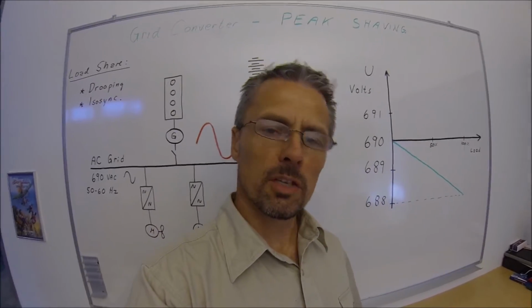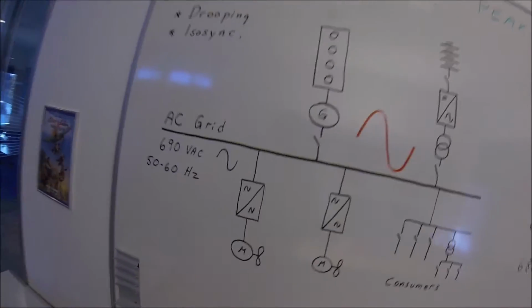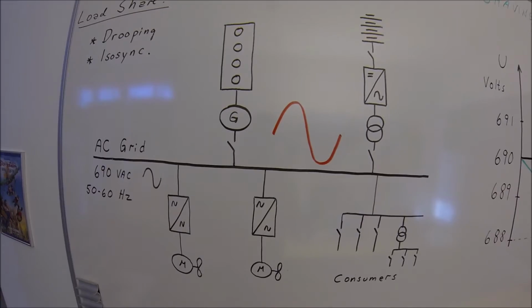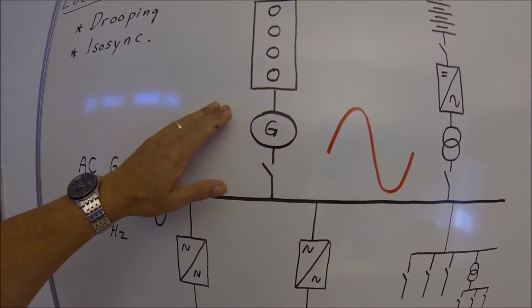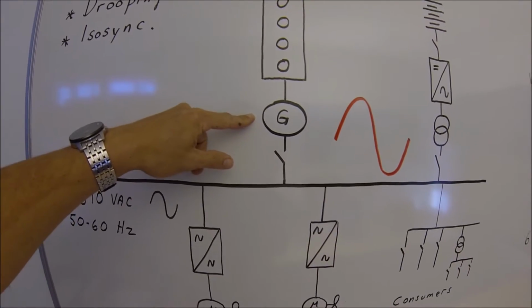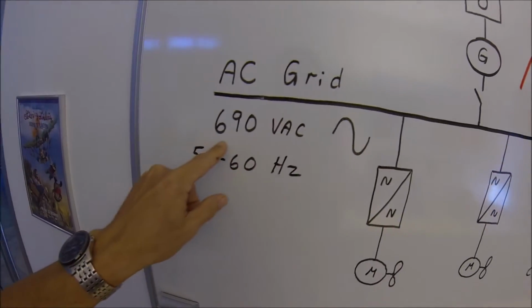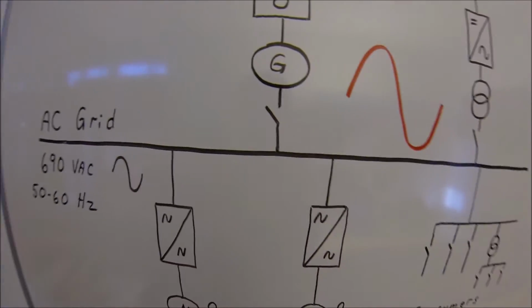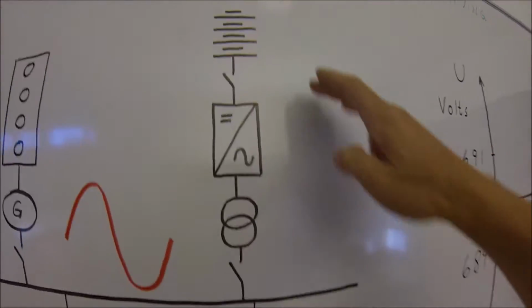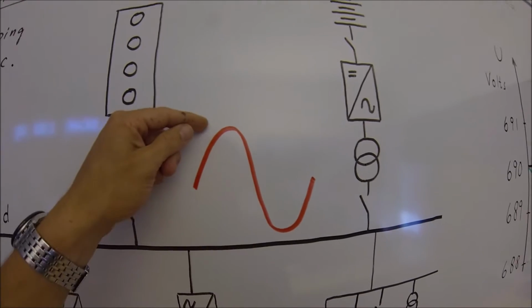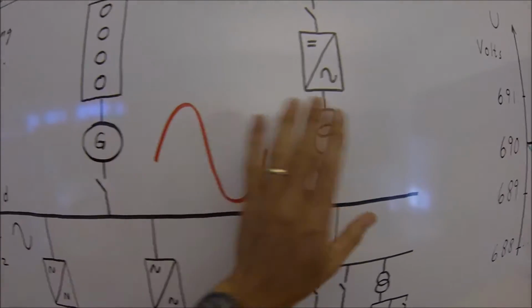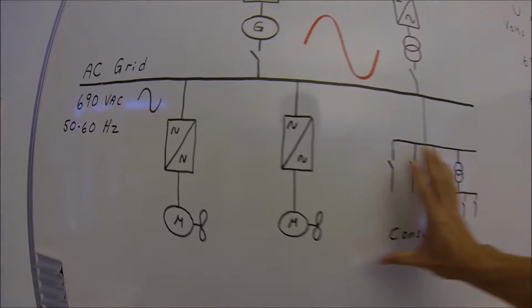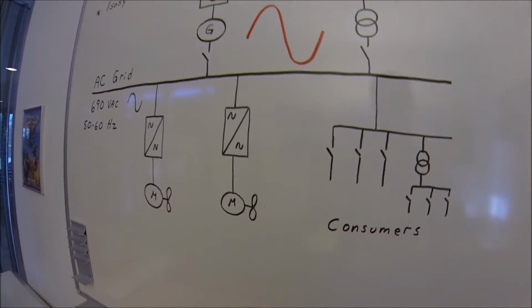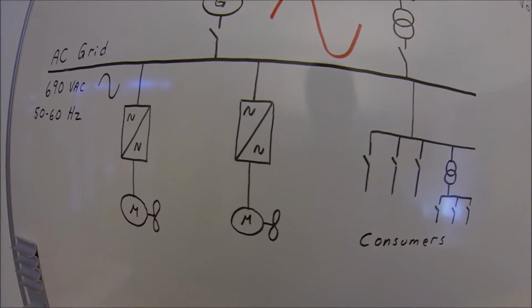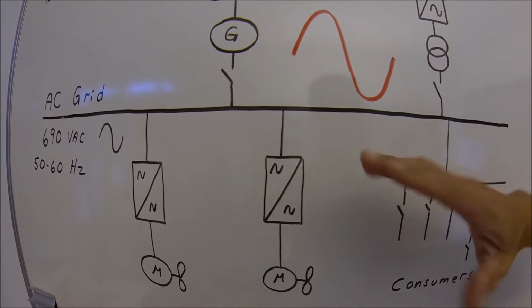What about the voltage on a ship grid? The nominal voltage is 690 volts. It means that these diesel generators have an automatic voltage regulator, a so-called AVR, that tries to aim for 690 volts. It means also that the energy storage aims for 690 volts, and the amplitude of the sinus should be totally equal. However, the ship consumers might have a reactive current going on, and also there will be voltage drop on the ship grid.